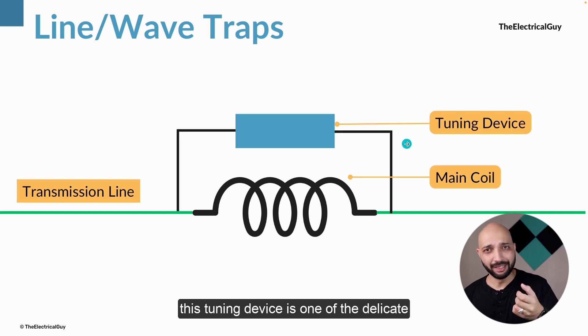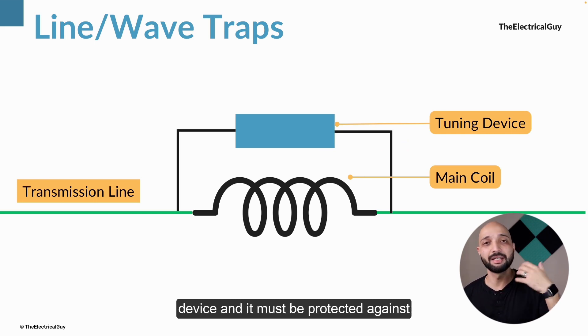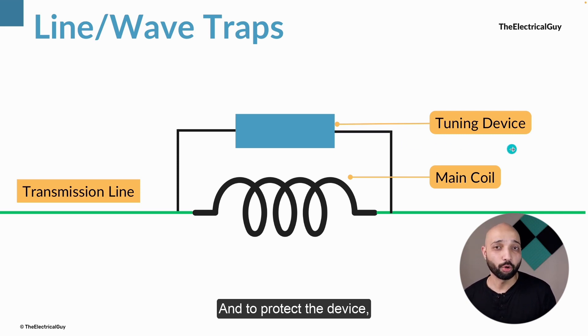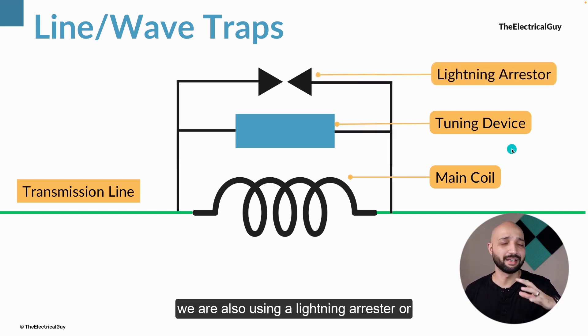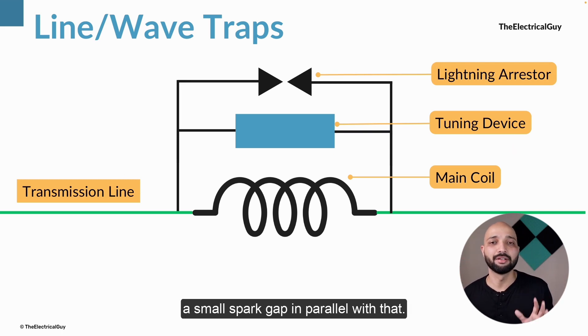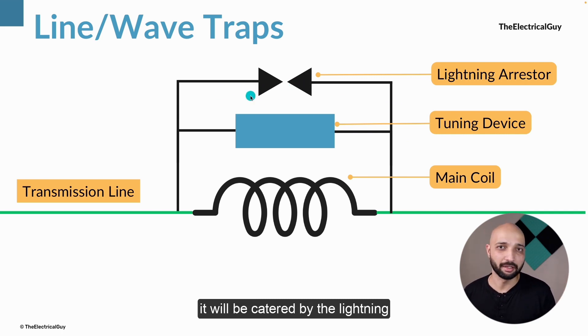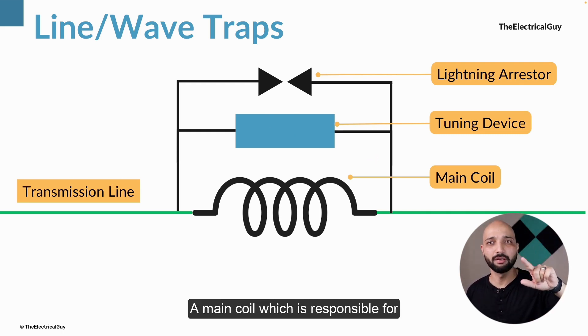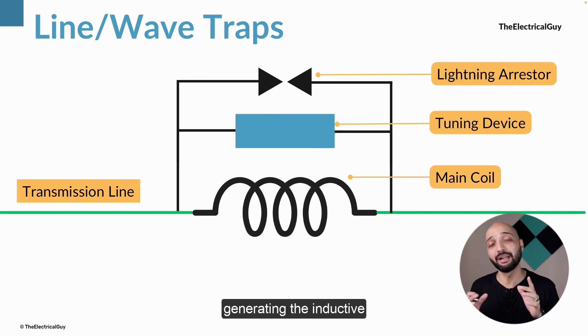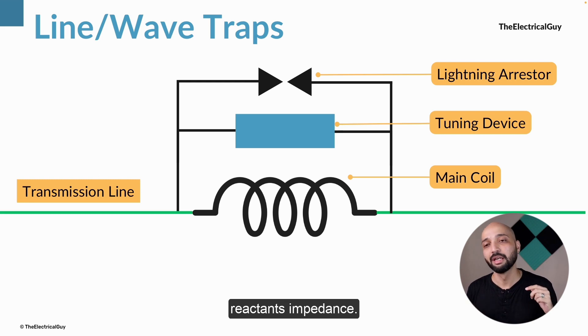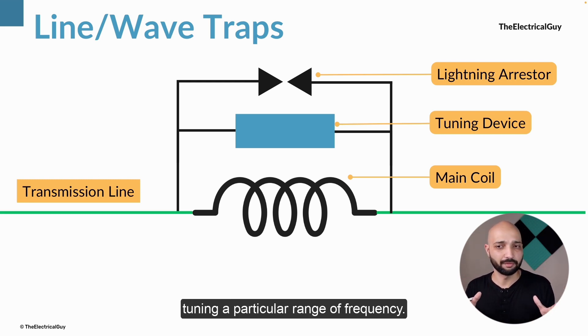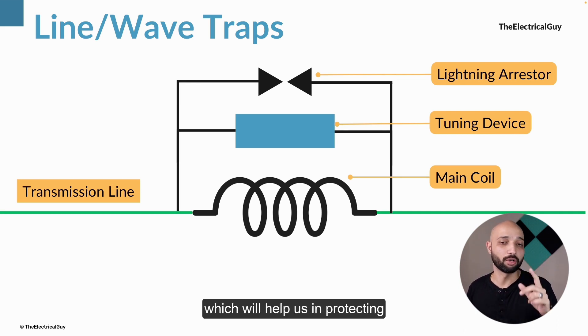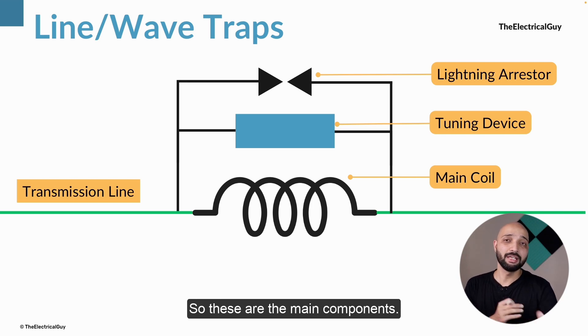The tuning device is a delicate component and must be protected against overvoltages. To protect it, a lightning arrester or a small spark gap is connected in parallel with it. In case a surge occurs, it will be handled by the lightning arrester and the device will be protected. So the basic components of a wave trap are: the main coil which generates inductive reactance, the tuning device which tunes a particular frequency range, and the lightning arrester or spark gap which protects the tuning device.